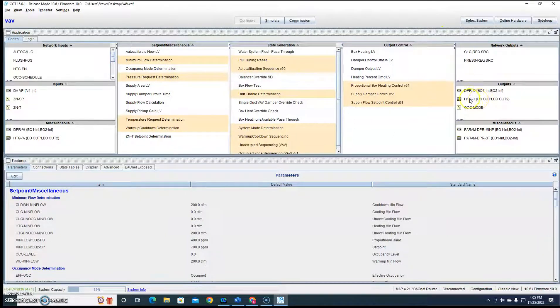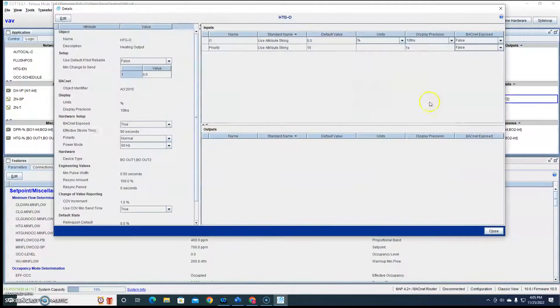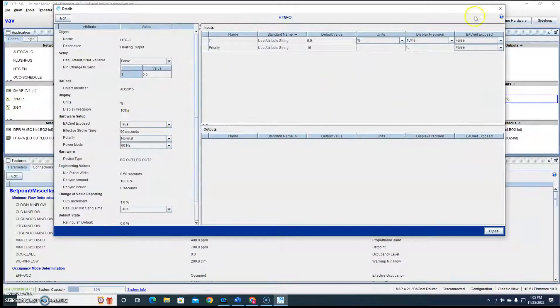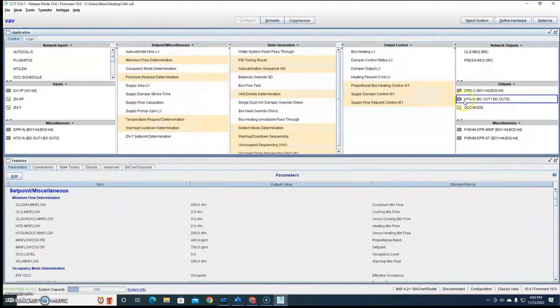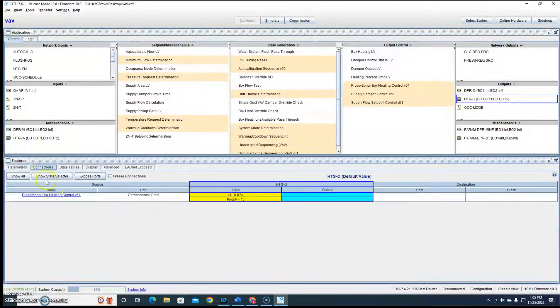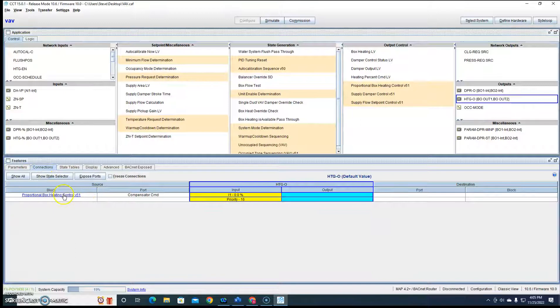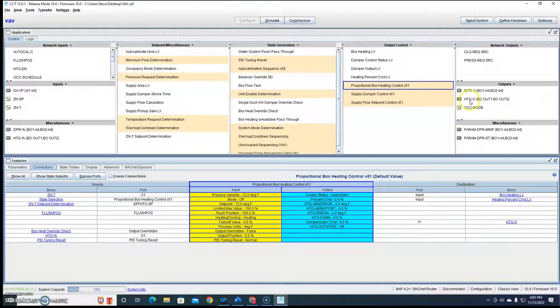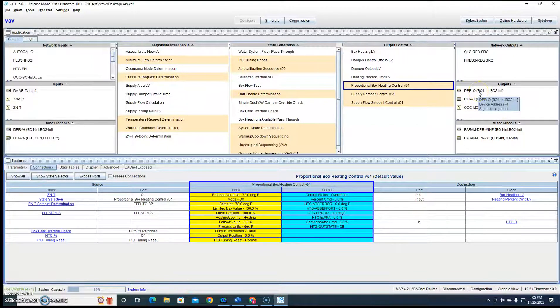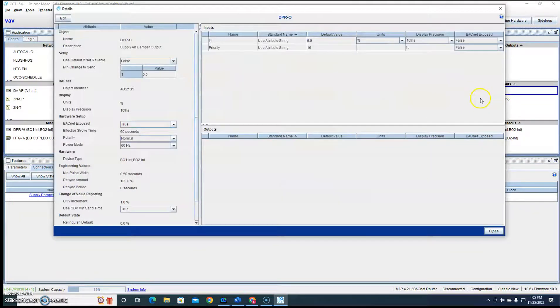And you're going to get a percentage, you're actually going to give a percentage signal to your command. So it's going to get that from proportional heating output. This guy right here is wired over to this hot water actuator, and that's what's going to drive it one way or the other.